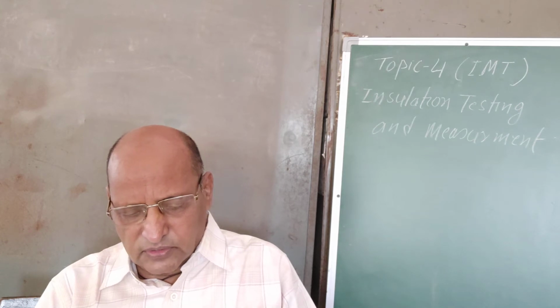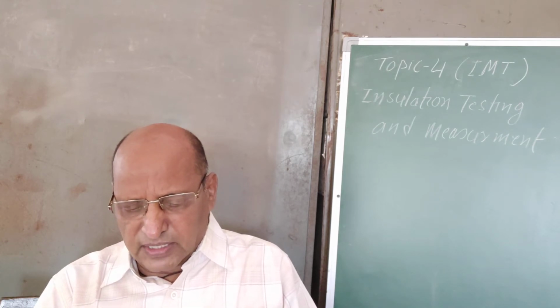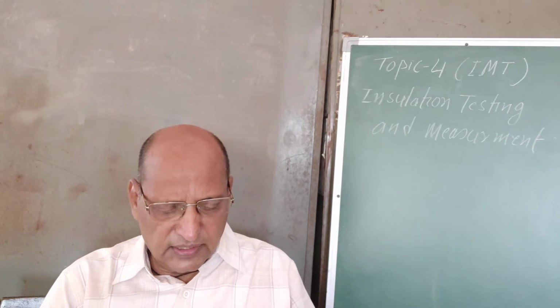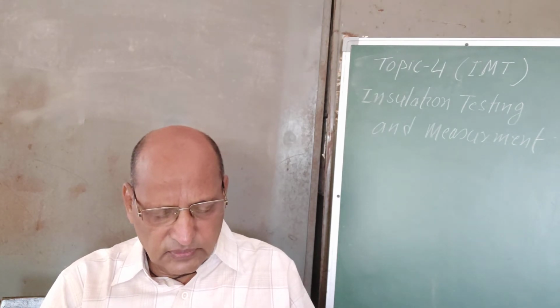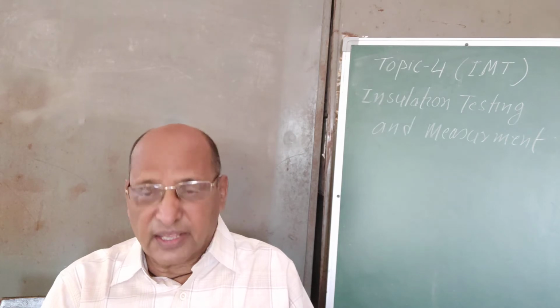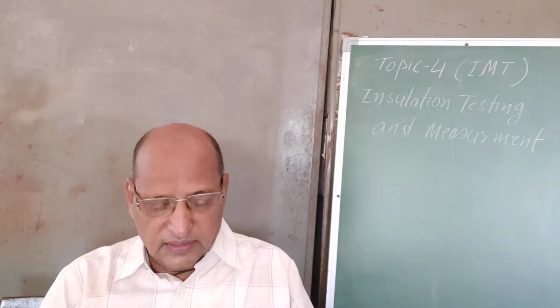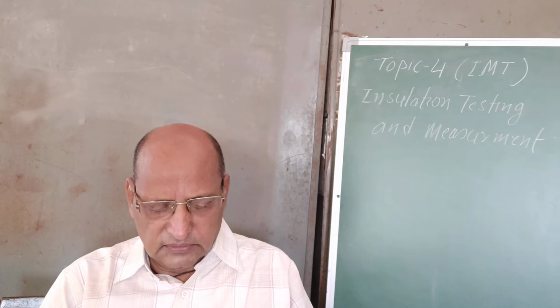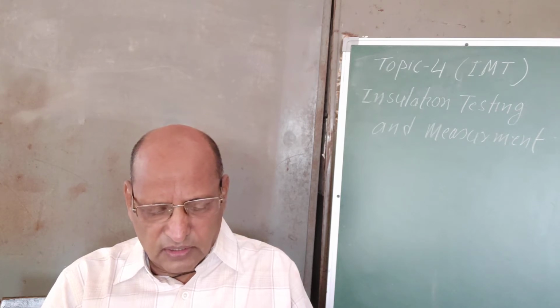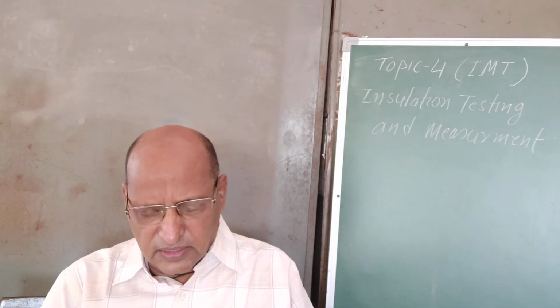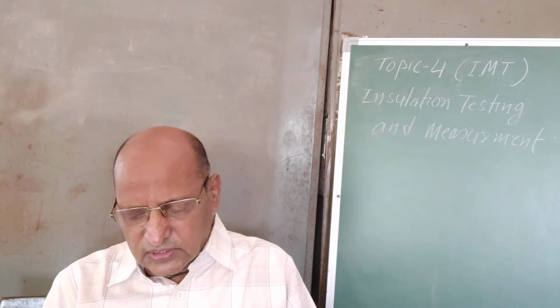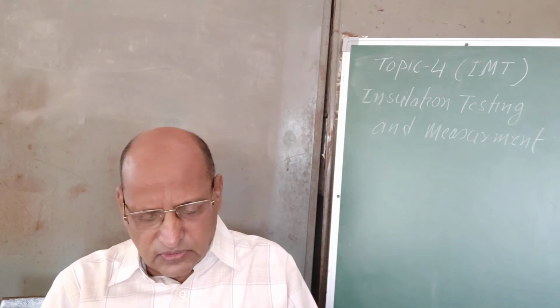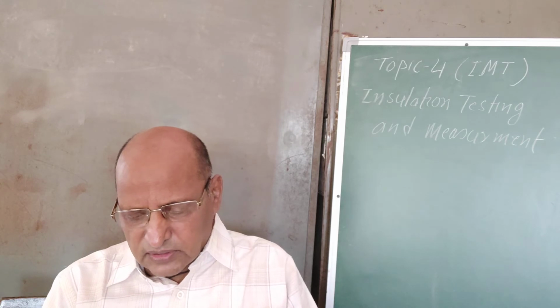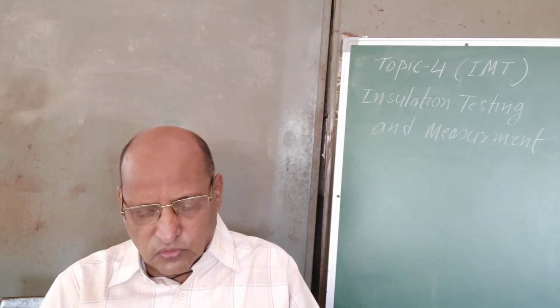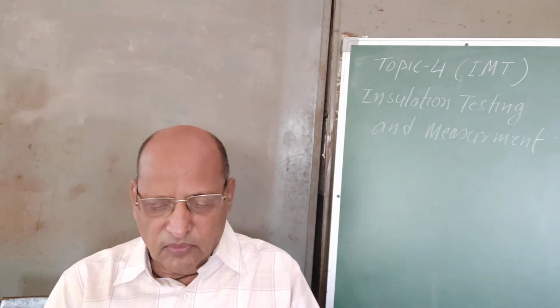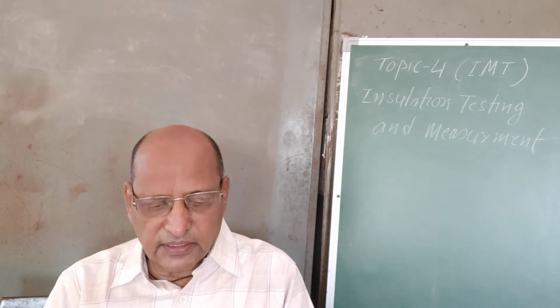Now, as I have told you, oil is one of the insulation materials used for all types of power equipment. Apart from the transformer, it is also used in different types of instrument transformers like CT, PT, and in other types of breakers, such as bulk oil circuit breakers and minimum oil circuit breakers. So these are the different types of breakers in which oil is used. As I have told you, the insulation level of oil is decided by its dielectric value.